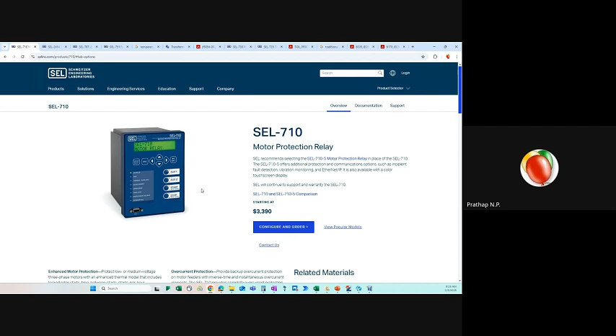Similarly, here, if you take this is a transformer monitor. This is not a transformer protection relay, but it's a transformer monitor. Same like the motor protection relay, it has communication capability, analog inputs, digital inputs, and RTD input. So it can take oil temperature, winding temperature, all those can come in. Now think how this was back in the 60s and 70s. It would be probably like this.